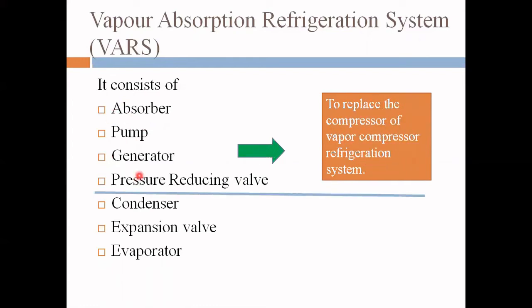The condenser, expansion valve, and evaporator are the same in both systems. These four components — absorber, pump, generator, and pressure reducing valve — replace the mechanical compressor of the Vapor Compression Refrigeration System. The mechanical compressor, such as a hermetically sealed compressor in a refrigerator or domestic AC, contains moving parts like a piston, cylinder, and connecting rod. Replacing it with these four parts gives us the VARS.